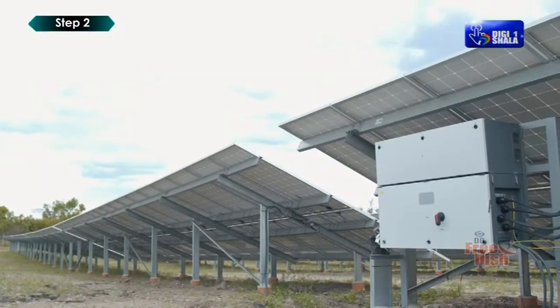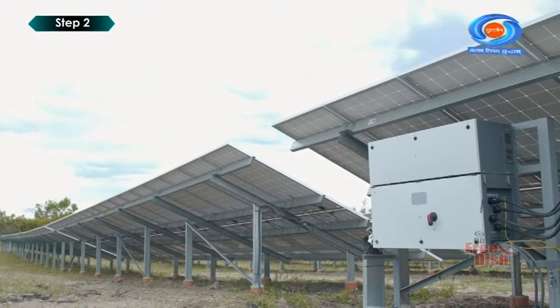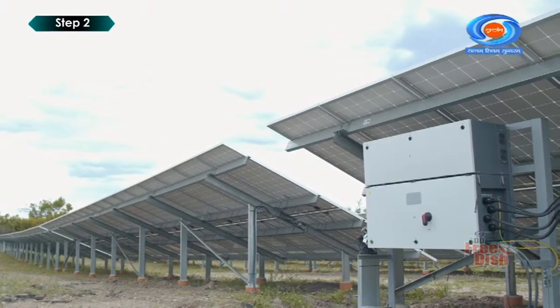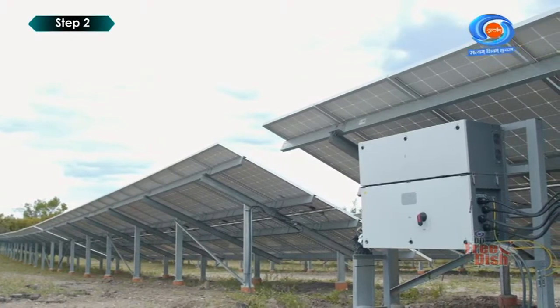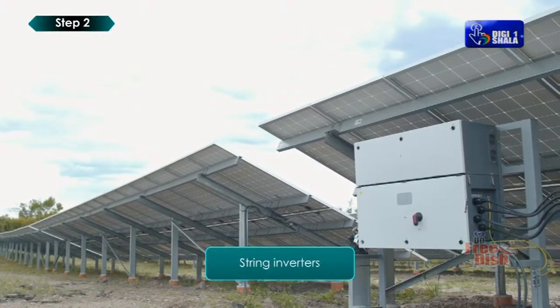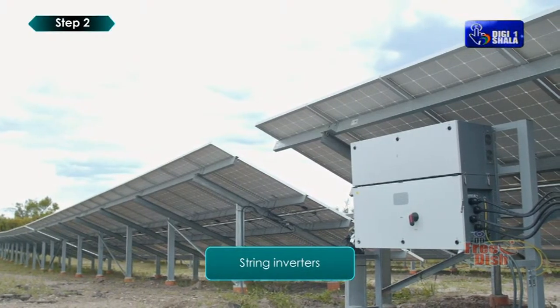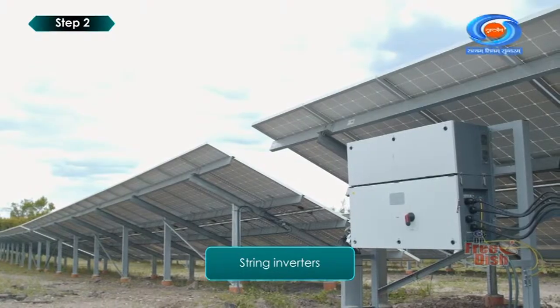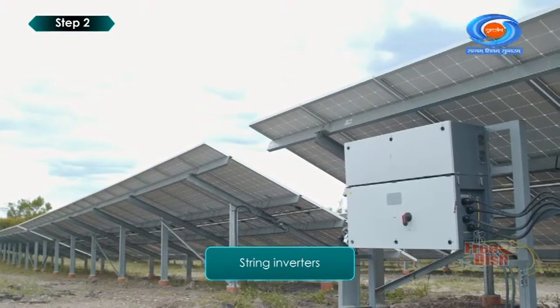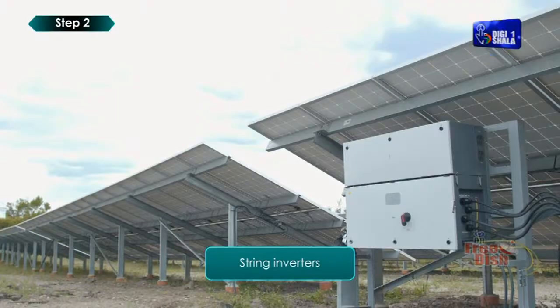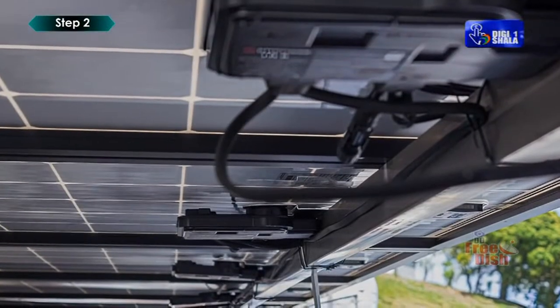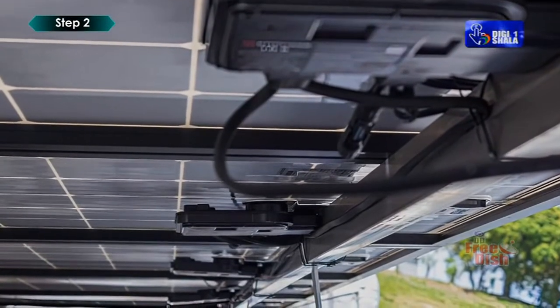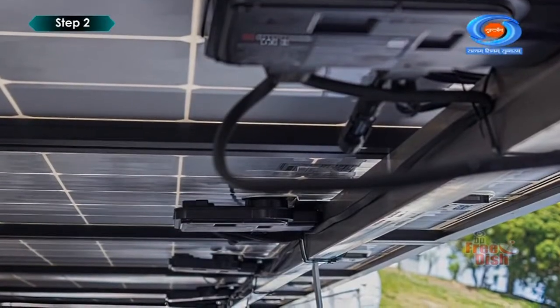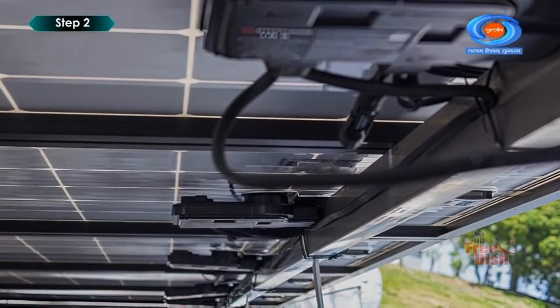In a large-scale utility plant or mid-scale community solar project, every solar panel might be attached to a single central inverter. String inverters connect a set of panels, a string, to one inverter. That inverter converts the power produced by the entire string to AC.